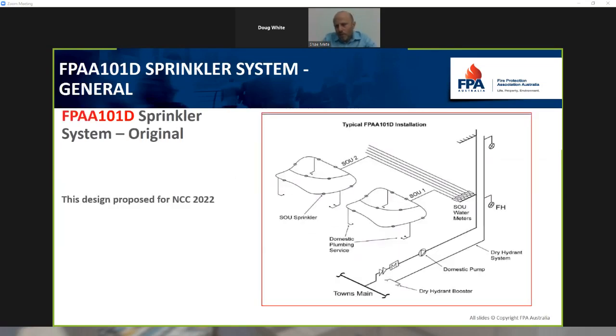Back at the very start, when I showed you the test that we did at CSIRO, we actually tested the system that's on the screen at the moment. This is different to the previous schematic, whereby you can see that the domestic plumbing service is tapped straight into the sprinkler system protecting the SOU. So these are taps, drinking water taps and showers and washing machines connected to the sprinkler system. That's how we tested it originally. And that was flowing through the SOU water meter.